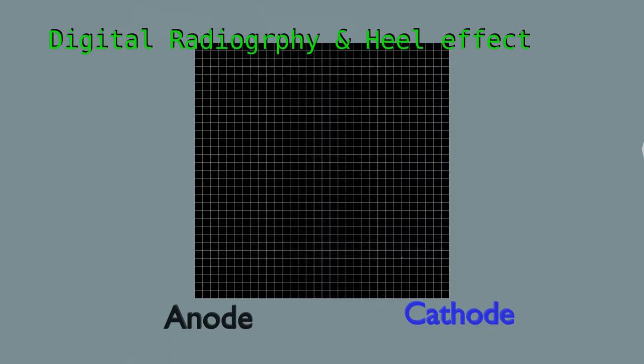In film screen radiography, anode cathode orientation of x-ray tube is significant to obtain distinguishable optical density on films. But, tube orientation is less significant in digital radiography. A uniform beam can produce a uniform grayscale value on a DR image.